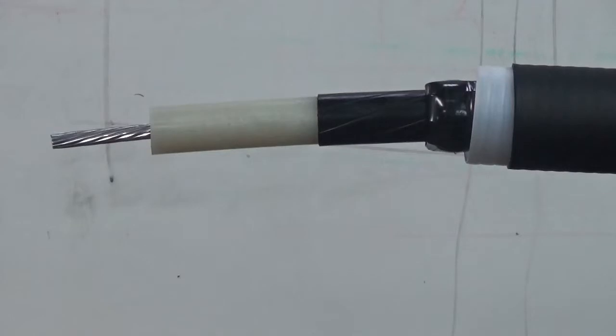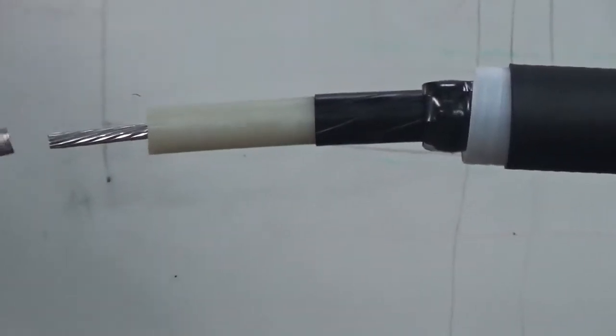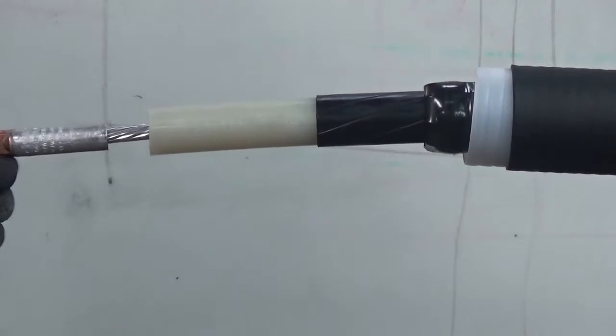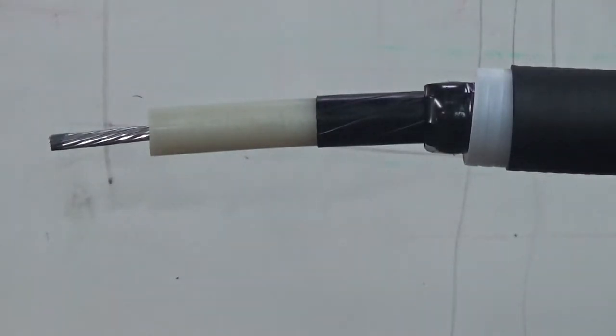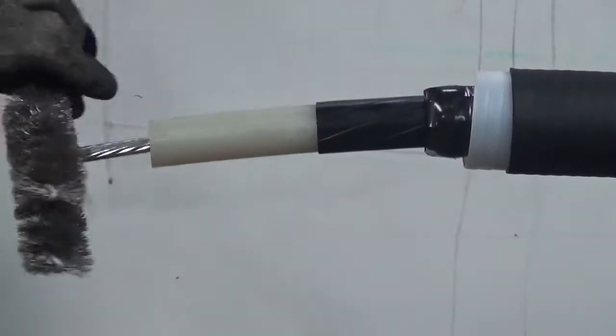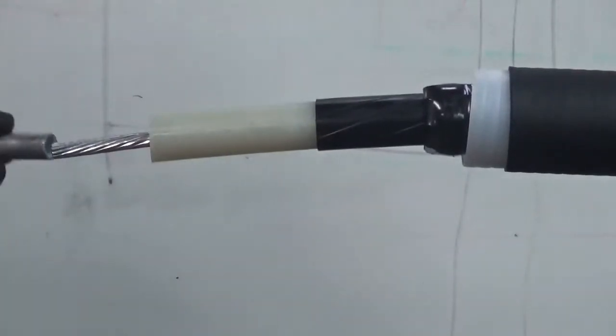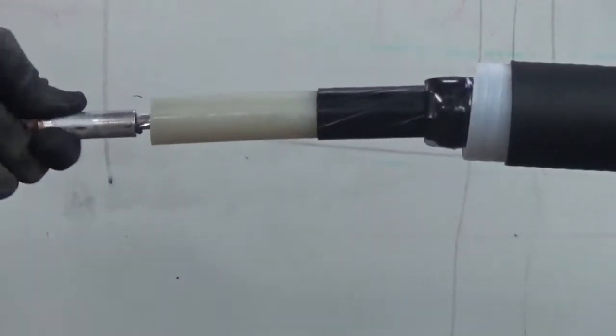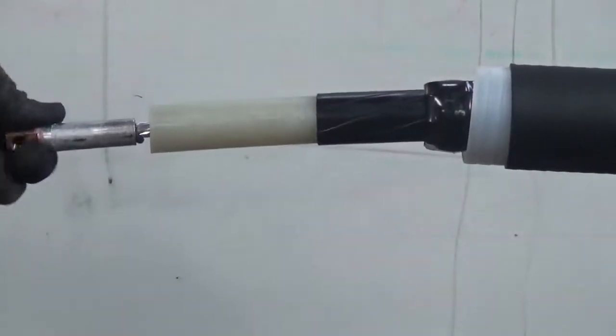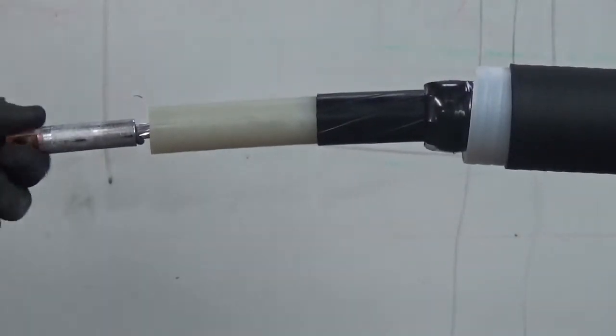You will use the lug with the kit, and when you put it on there, if you're on a transformer, a boot station or what have you, you want to make sure you have that lined up properly before you put your lug on. So when you're ready, go ahead and wire brush the aluminum, and then slide your lug on. The aluminum does start to oxidize immediately, but as you can see the grease in there will help prevent the oxidation.